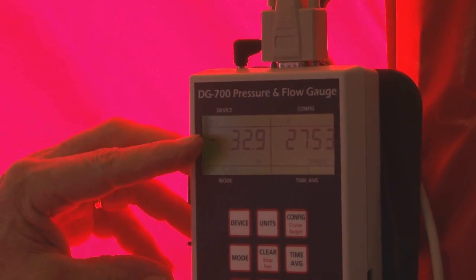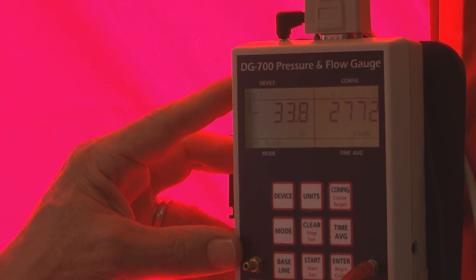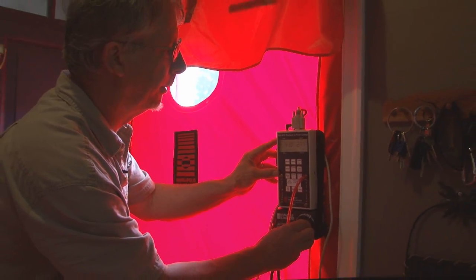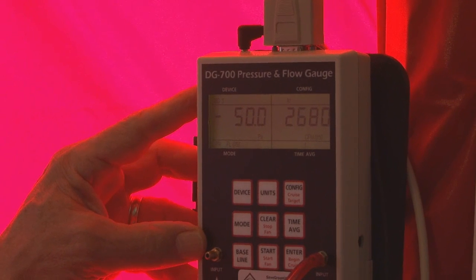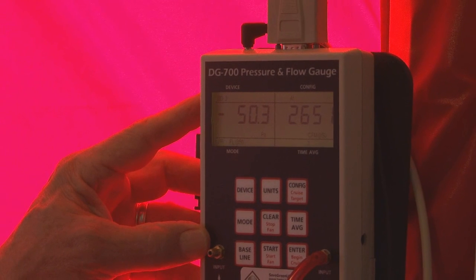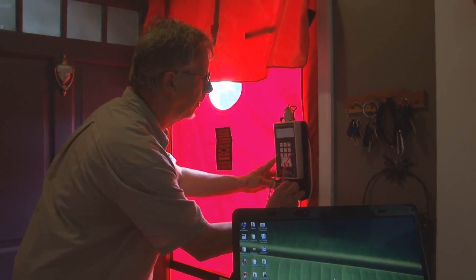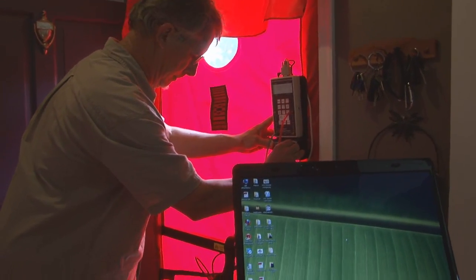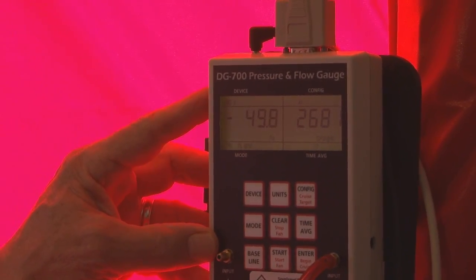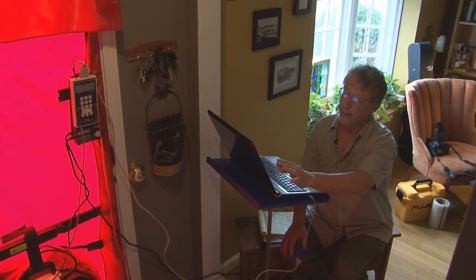This is the Pascal measurement — I'm going to 50. This is the CFM that's flowing across the blower door. A tight home is 1,200 CFM or less — Andrew's house is 600. The Wilson house measured 2,650 CFM at 50 Pascals. When a tight house is below 1,200 and Andrew's house is 600, the Wilson house has a long way to go. The pressure testing continued, both manual tests and computer-controlled tests. At one point, Andrew had this sobering bit of information for us.